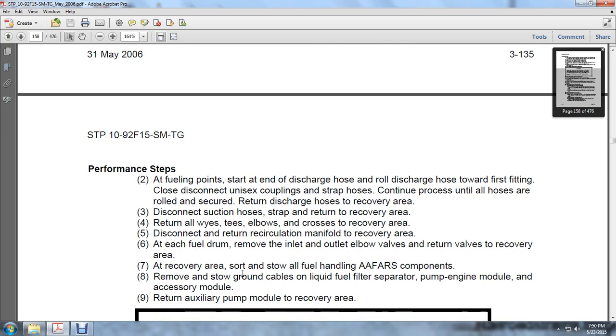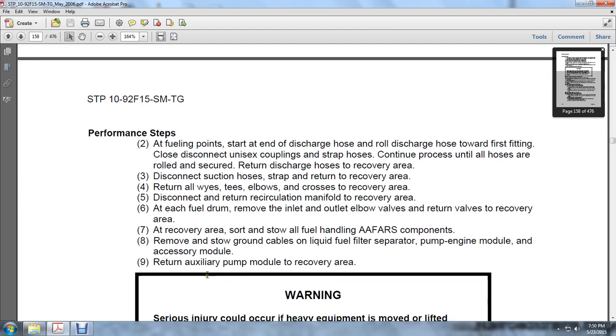Return them to the recovery area. Return all Ys, Ts, elbows and crosses to the recovery area. Disconnect and return the recirculation manifold to the recovery area. At each fuel drum, remove the inlet and outlet elbow valves and return the valves to the recovery area. At the recovery area, sort and stow all advanced aviation forward area refueling system fuel handling components. Remove and stow ground cables on liquid fuel filter separator, pump engine module, and the accessory module. Return the auxiliary pump to the recovery area.